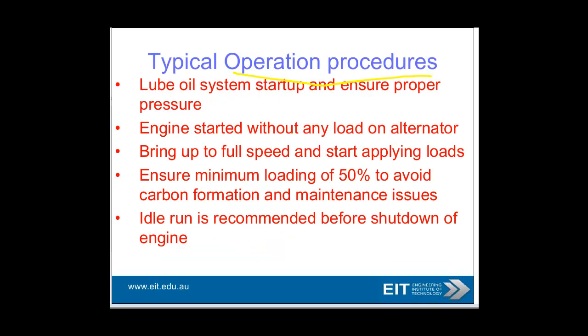Typical operation procedure: with the lube oil system at startup, ensure proper pressure. Then you start without any load, of course, otherwise you won't be able to get going. Bring up to full speed, start applying load slowly, and ensure that you've got a minimum loading of about 50% to prevent maintenance issues such as carbon formation in the engine. An idle run is recommended before shutdown. In other words, you take the load off and run it for a while before you shut it down. So a pretty established procedure.